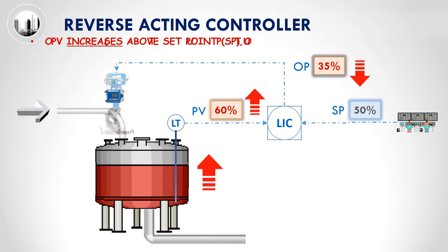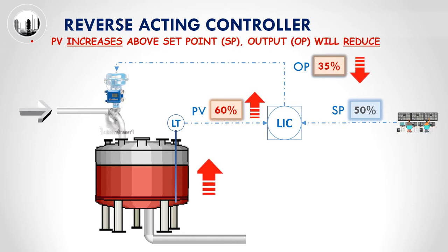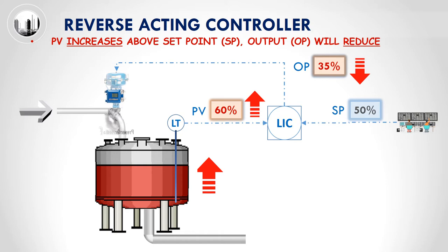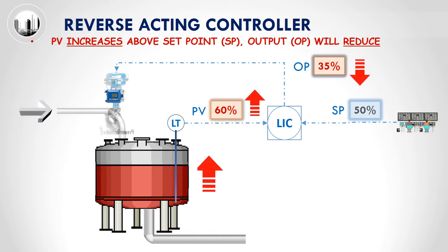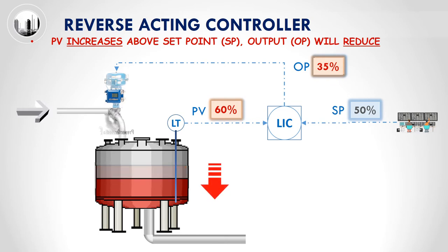Thus, for a reverse acting controller, when the current process variable or PV increases above the set point or SP, the output or OP will reduce. With the smaller opening of the control valve, the tank level will reduce back to the set point.